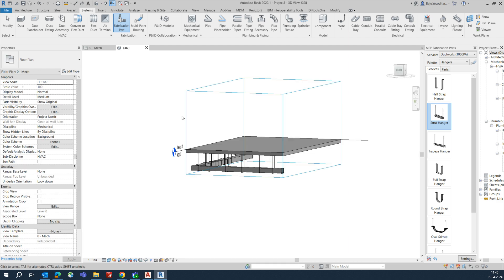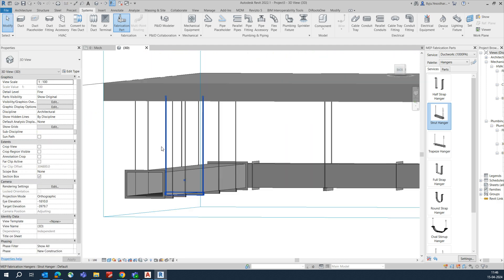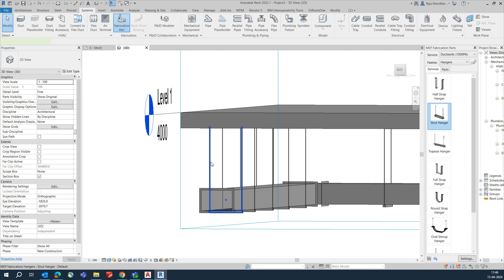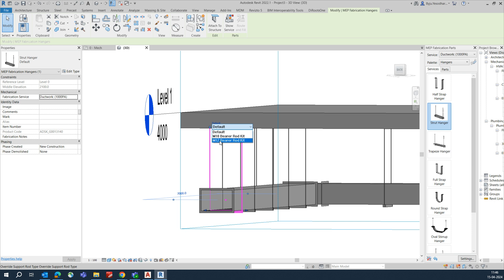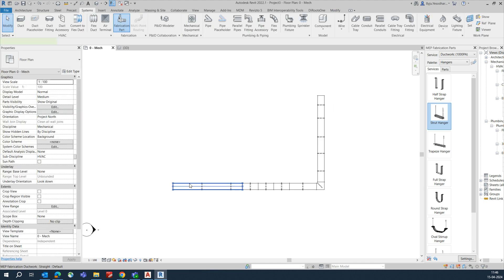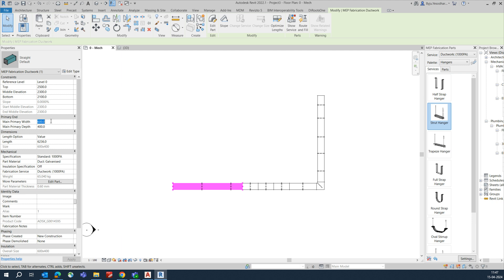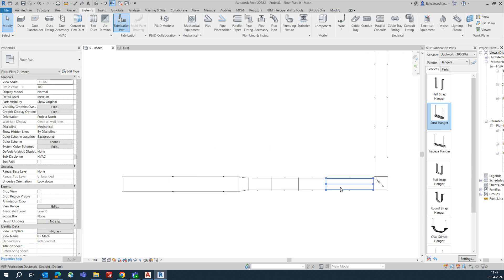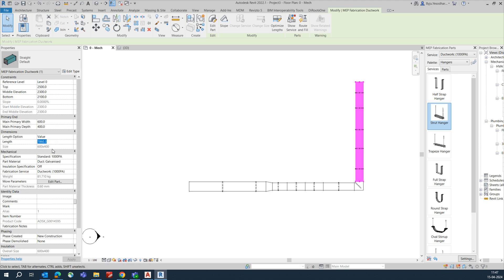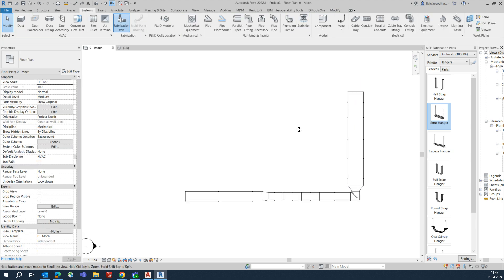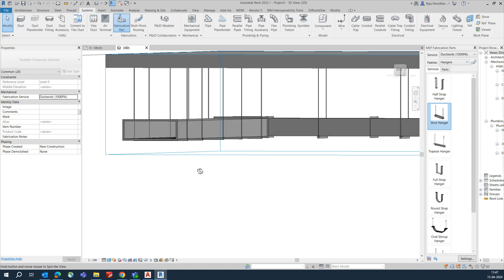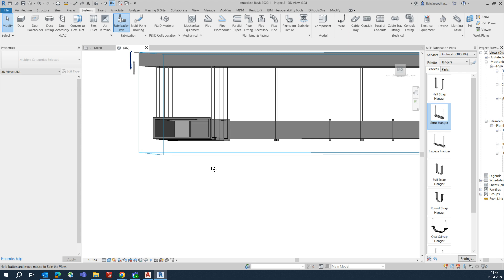In the 3D view, you can see the supports are automatically fixed to the ceiling. You can select a support and change its type, for example to M12. You can also change the primary width — for instance, setting it to 750 or 1200 — and the support will automatically adjust to match that width.